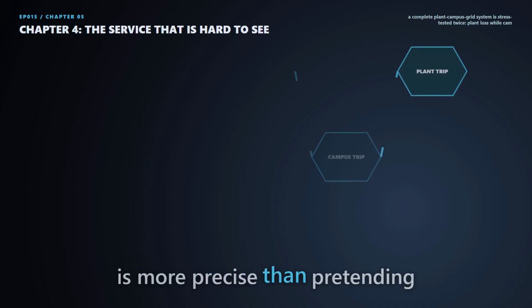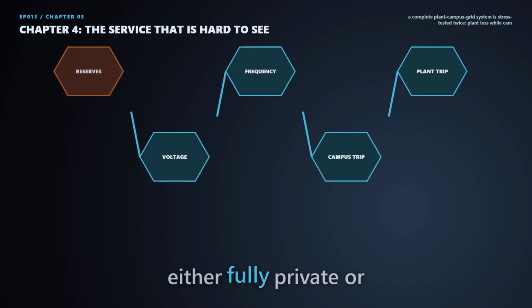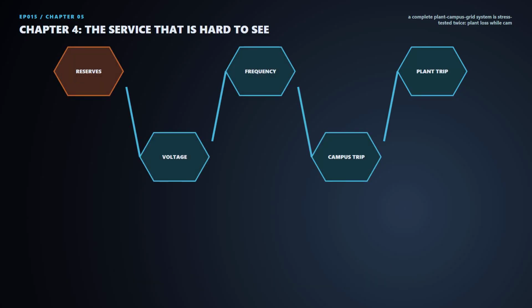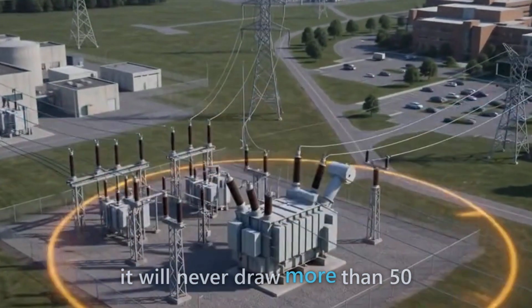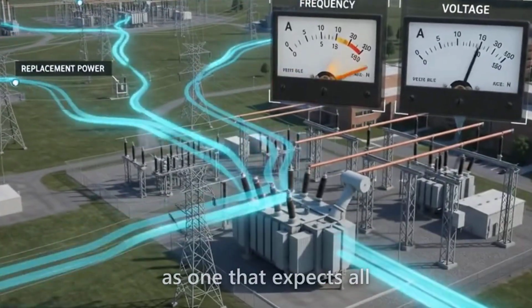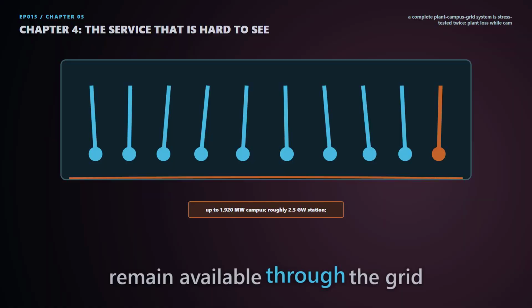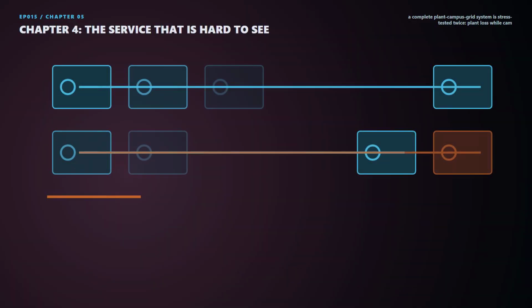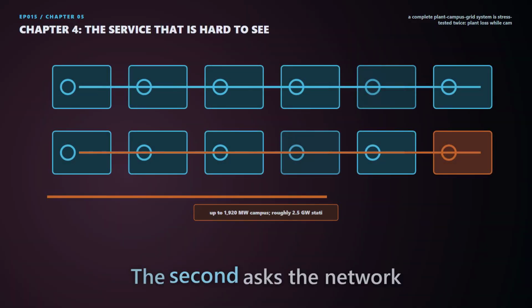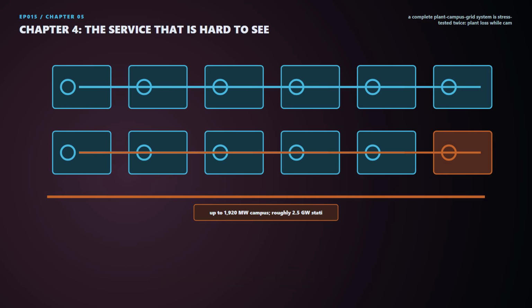This is more precise than pretending every co-located load is either fully private or an ordinary network customer. A campus that guarantees it will never draw more than 50 megawatts from PJM does not need the same service as one that expects all 500 megawatts to remain available through the grid after the plant trips. The first can accept curtailment. The second asks the network to act as a full backup power source.